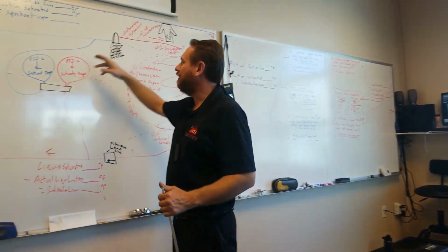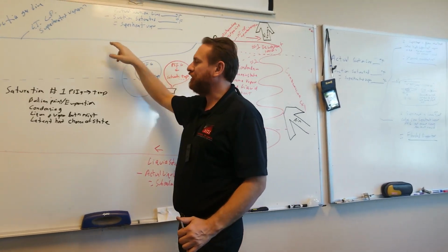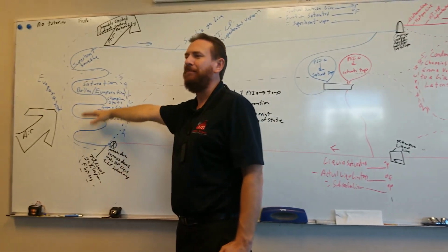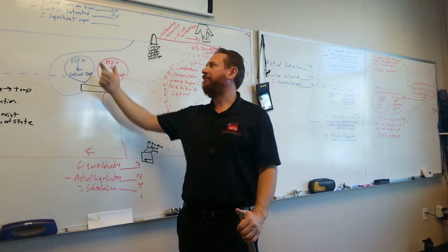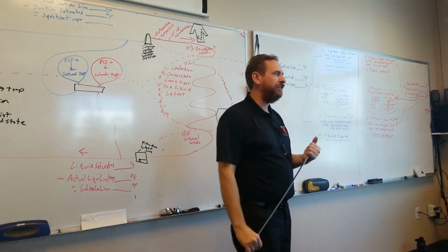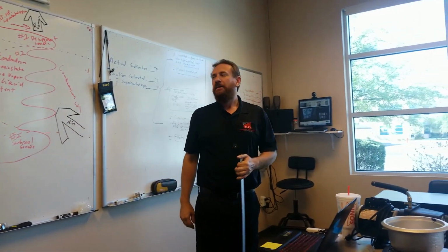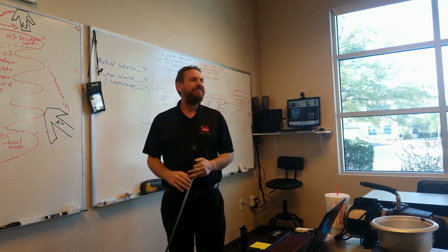If I let it run for less time and the unit shuts off, that oil may start building up in the evaporator or over here in this other line, and the oil doesn't make its way back to the compressor, and the compressor starts up without oil. So you want that compressor to have a certain amount of run time.